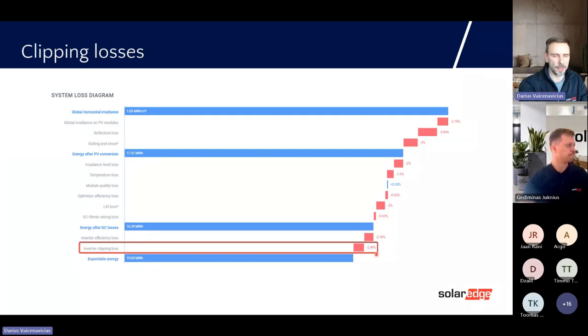But in the end, we decided that we still have to install proper cables and proper circuit breakers, because usually the design is done according to the equipment label. So if the inverter is 100 kW, you need to design the cables accordingly, so they can withstand 100 kW of AC power, and the circuit breakers as well. So if you are undersizing inverters, you will usually have higher AC grid costs as well. So it doesn't make sense to undersize the inverters.